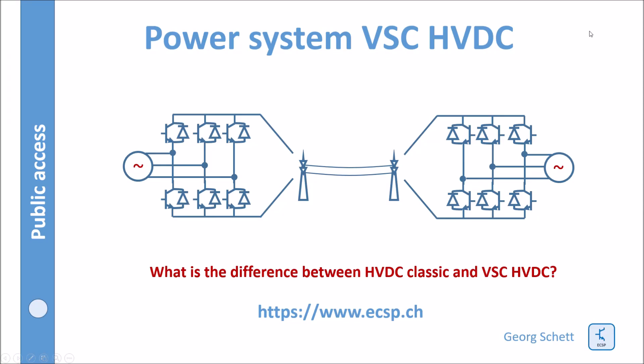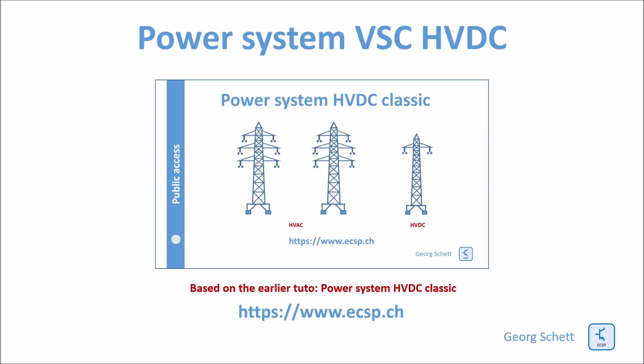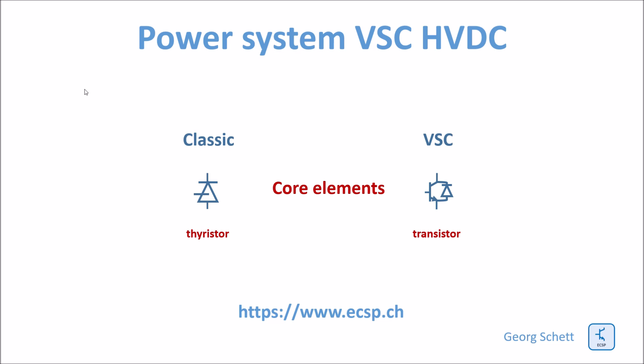Let's talk about the voltage source converter HVDC technology and compare it to HVDC Classic. The VSC technology is more modern. The big advantage is it can be used for black starts — it can feed power into a network which does not provide an active source. This is the key difference to HVDC Classic, where you need an active load with an existing power source. The core switch of HVDC Classic is a thyristor, whereas for VSC HVDC the core element is a transistor.